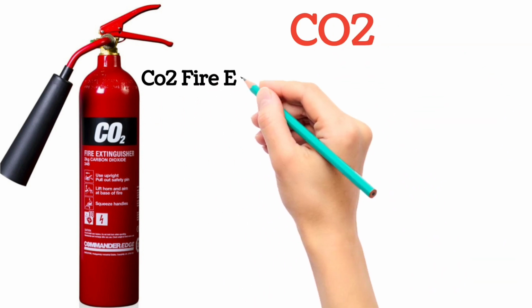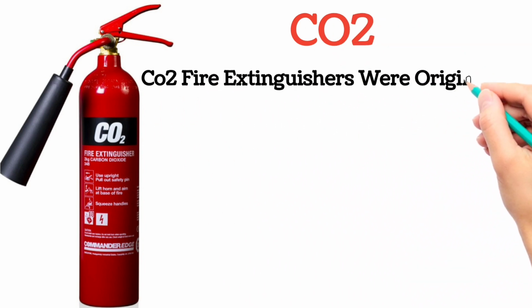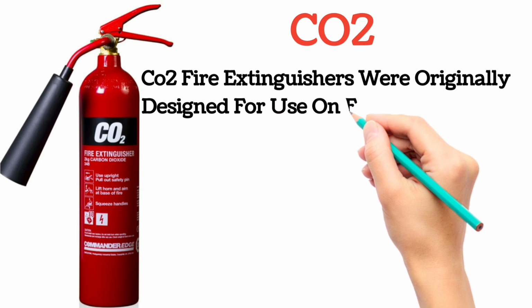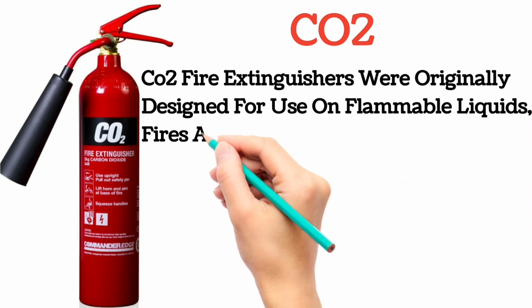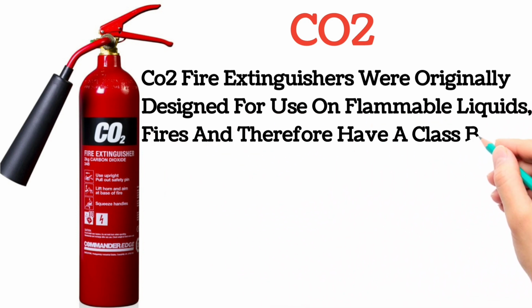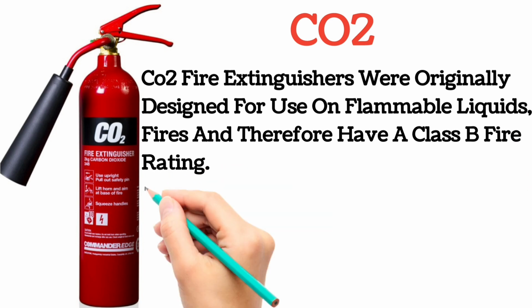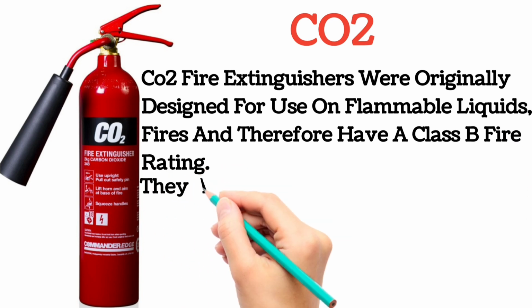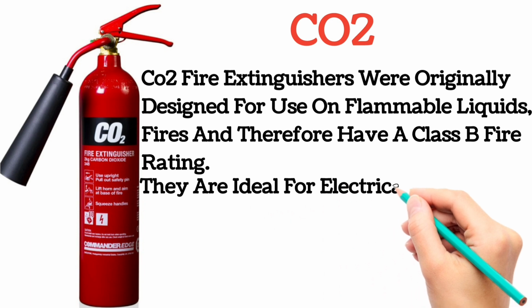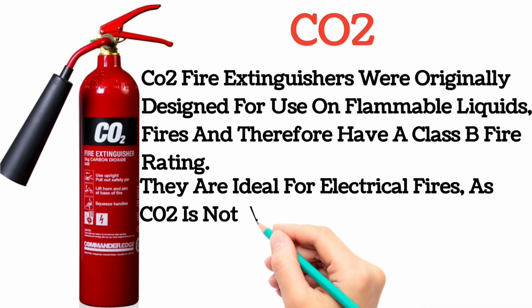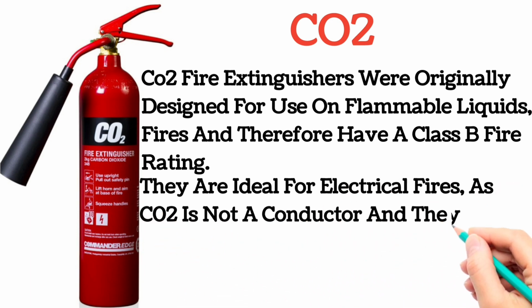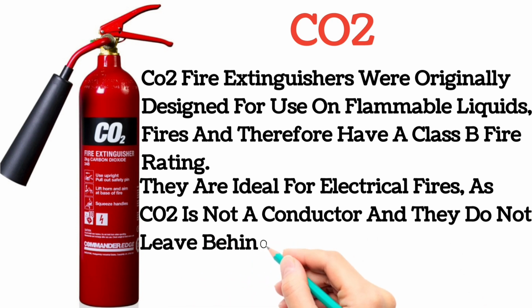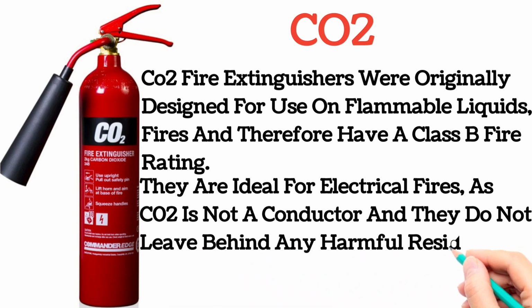CO2 fire extinguishers were originally designed for use on flammable liquid fires and therefore have a Class B fire rating. They are ideal for electrical fires as CO2 is not a conductor and they do not leave behind any harmful residue.